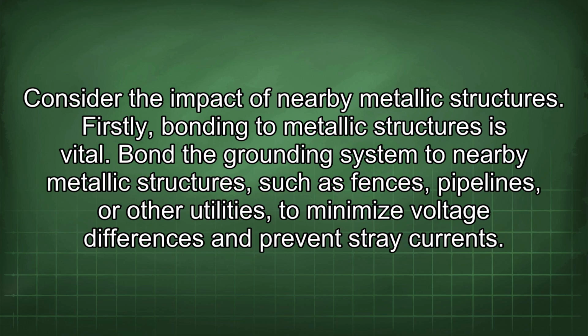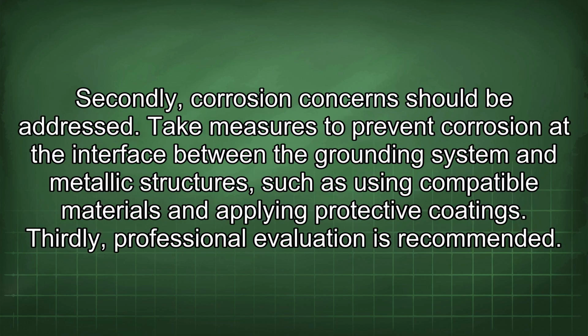Consider the impact of nearby metallic structures. Firstly, bonding to metallic structures is vital. Bond the grounding system to nearby metallic structures, such as fences, pipelines, or other utilities to minimize voltage differences and prevent stray currents. Secondly, corrosion concerns should be addressed.